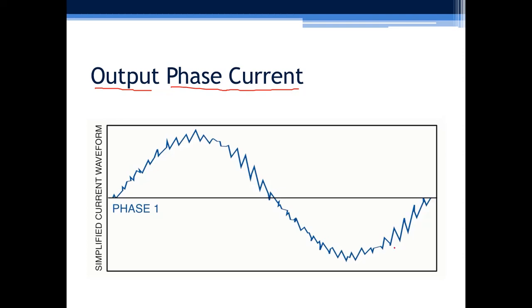There are certain harmonics that remain, but we have taken THD to a very low level, that is 3 to 4%, and as the nature of current has become closer to sinusoidal, the performance of this inverter will be much better than the voltage source inverter. As we get sinusoidal current, we will get precise torque, constant torque, and better performance of the 3-phase induction motor.